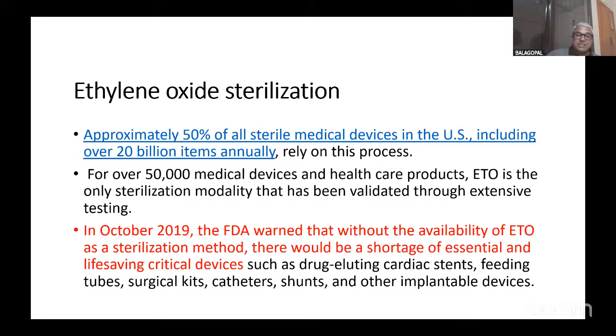It's a colorless gas with a sweet odor and is flammable and explosive. There are 4 essential parameters for the effectiveness of ETO sterilization: the gas concentration, the temperature at which it is to be done, the relative humidity, and the exposure time, which ranges from 1 to 6 hours. Approximately, US statistics say that about 50% of all sterile medical devices, including over 20 billion items, rely on this process. And way back in October 2019, the FDA warned that without the availability of ETO as a sterilization method, there will be a shortage of essential life-saving critical devices like drug-eluting cardiac stents, feeding tubes, catheters, etc.